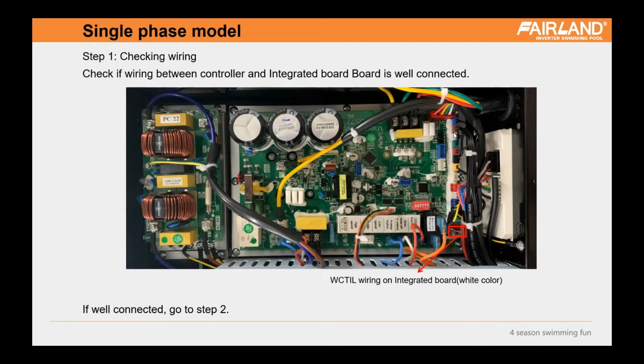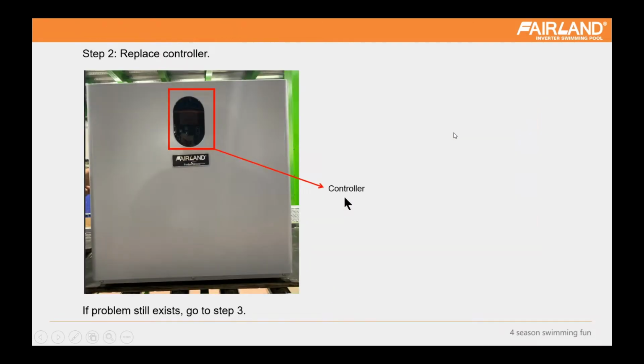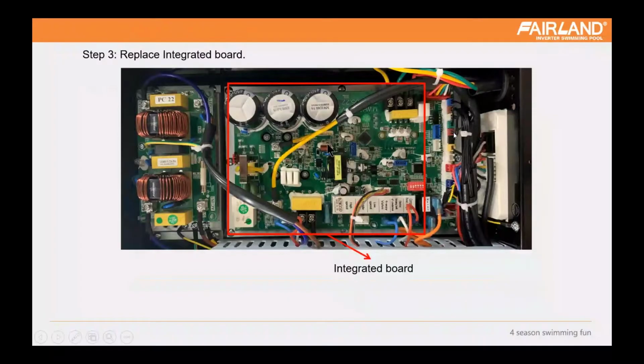PGLO is about the controller and the integrated board. We will firstly check whether the wire between the controller and the integrated board is well connected. Next, we have to replace the controller, because replacing the controller is a simpler, easier operation, so we will replace the controller first. And step 3, we will replace the integrated board. So we will check this whole communication system to see if the wire has a problem.